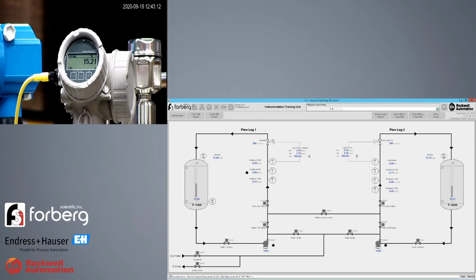on tank 200 in our system. This device is a 4 to 20 milliamp analog level transmitter, and like the majority of E&H's line of analog transmitter, this device provides HART device and diagnostics data. The HART protocol has been around since the mid-'80s and provides digital data that is imposed on top of the 4 to 20 milliamp current loop. Through the preferred integration mentioned earlier, and without any added programming, the operation and maintenance personnel are provided with additional process variable and diagnostics that can be used in the process control system.